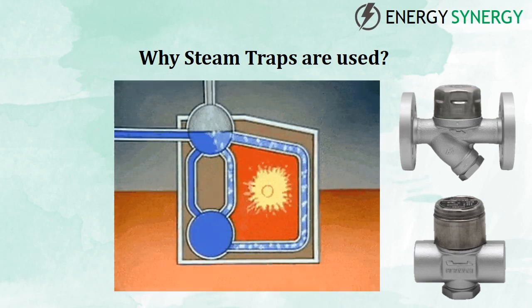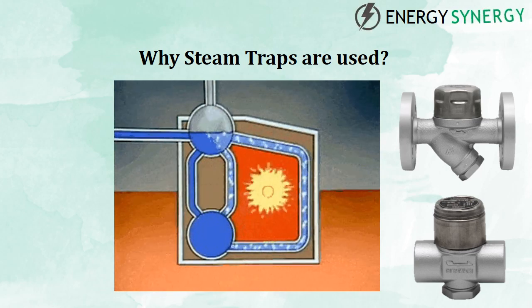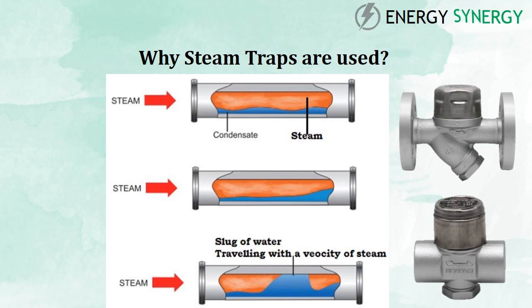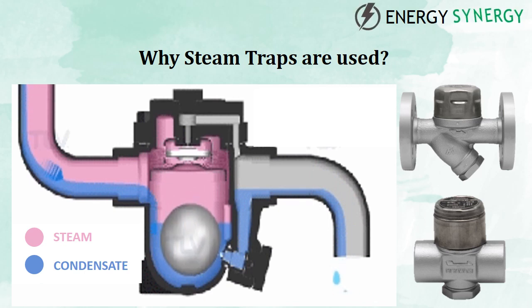Steam generated by a boiler contains heat energy which is used to heat the product. When steam loses its energy by heating the product, condensate is formed. Also, a part of the energy contained by steam is lost through radiation losses from pipes and fittings. After losing this heat, steam gets converted into condensate. If this condensate is not drained immediately as soon as it forms, it can reduce the operating efficiency of the system by slowing the heat transfer to the process. Presence of condensate in a steam system can also cause physical damage due to water hammer.